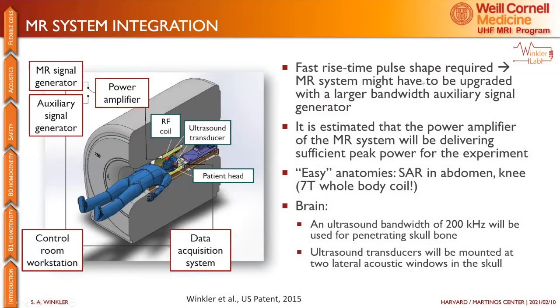All right. In order to integrate that into the scanner, you need to do a few things. It's not too bad. You need a fast rise time for this. So you might just use a different signal generator. The power might be good enough. I did a first estimation, and it might work out. You could start with easy anatomies that don't have the skull aberration, for example, the abdomen or the knee. And for the brain, actually our bandwidths are pretty low, so this might even work in terms of penetration of the skull bones. And we can also mount the ultrasound transducers at the lateral acoustic windows.